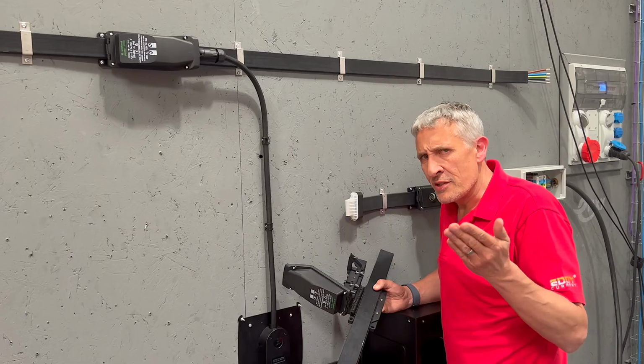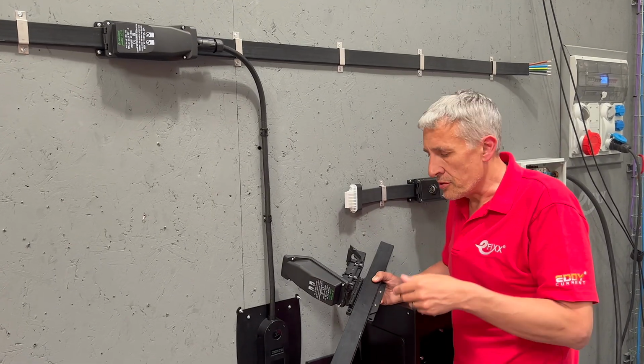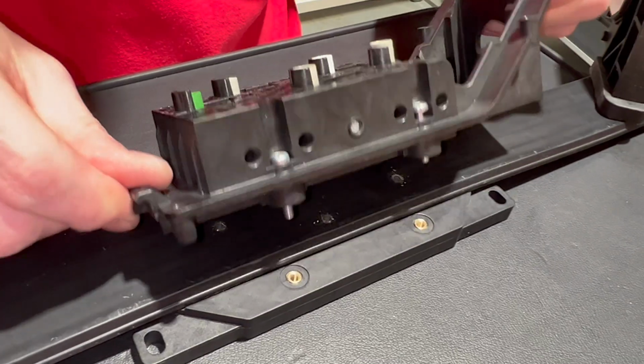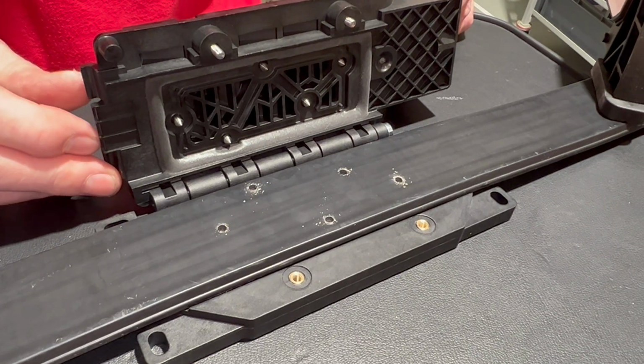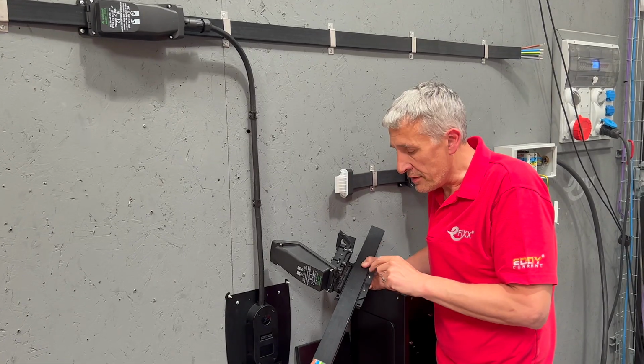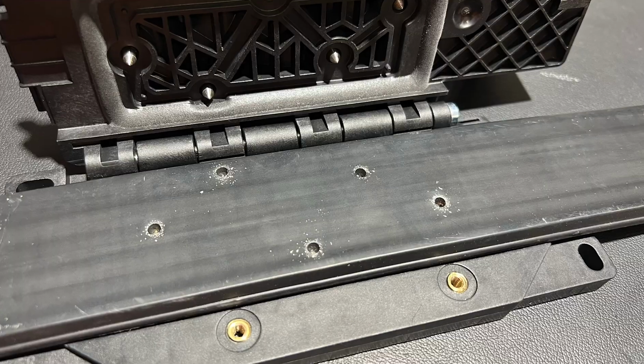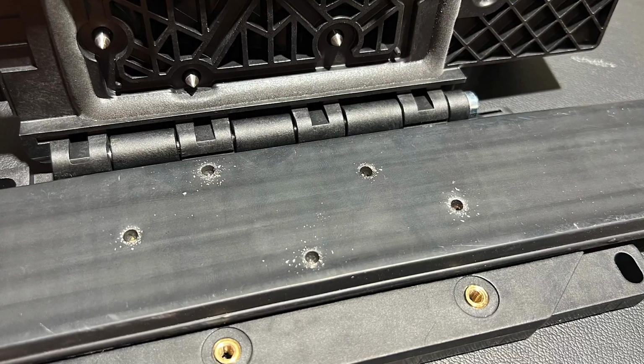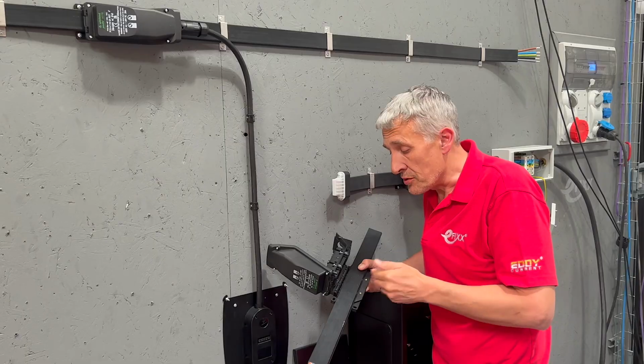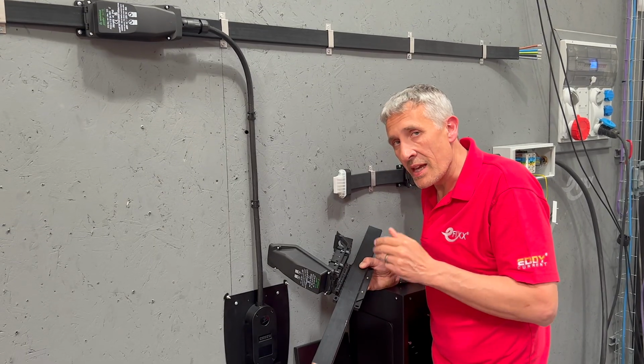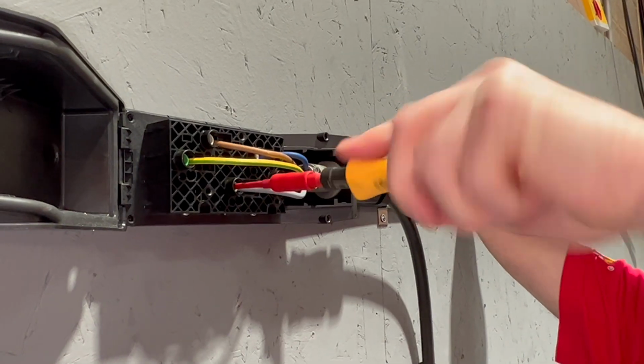Now, of course, when we say screws, these aren't just any old screws. Wieland define this as insulation piercing technology, and the screw itself has been very carefully designed to make the exact contact point to the cable, and you can't drive it any further than that. So the risk of getting this wrong is absolutely minimum. Just follow those torque settings.